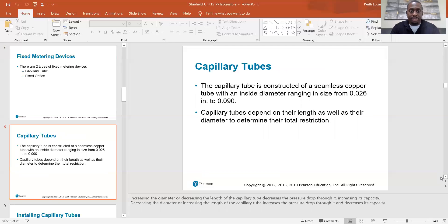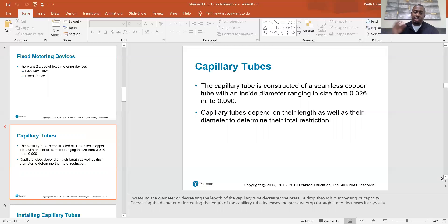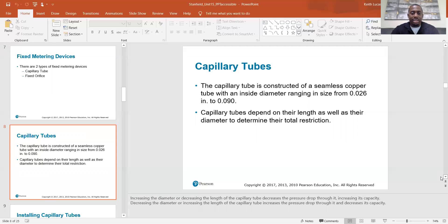Capillary tubes are the same in principle but made differently. A capillary tube is constructed of seamless copper tube with an inside diameter ranging from 0.026 inches to 0.090 inches. Capillary tubes depend on both their length and diameter to determine their total restriction. Increasing the diameter or decreasing the length increases the capacity; decreasing the diameter or increasing the length increases restriction and decreases capacity.